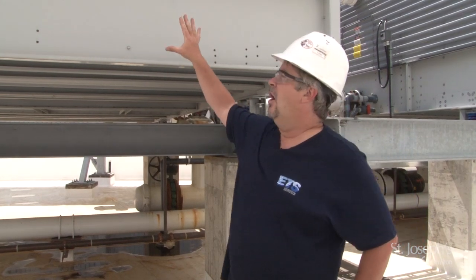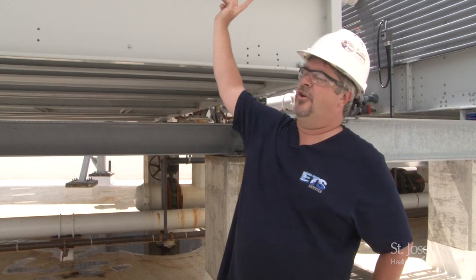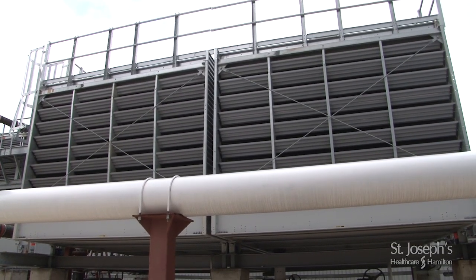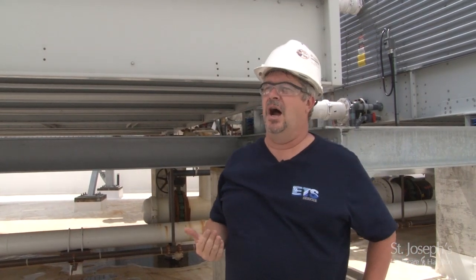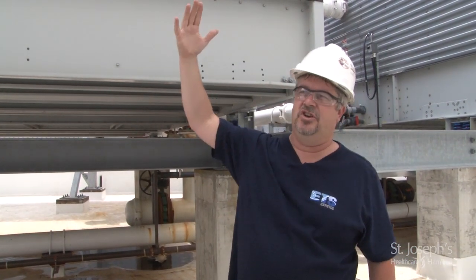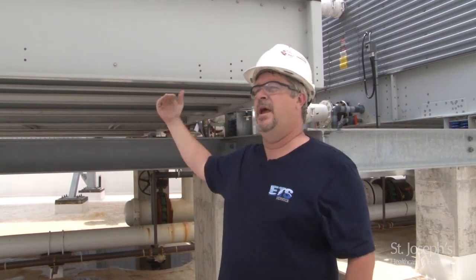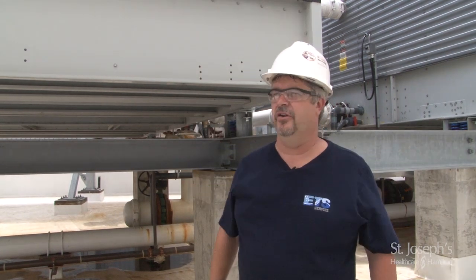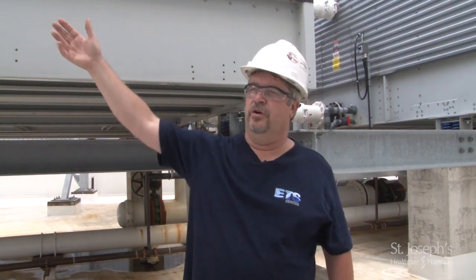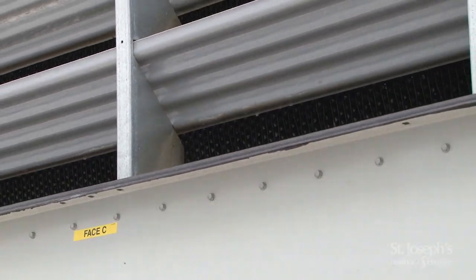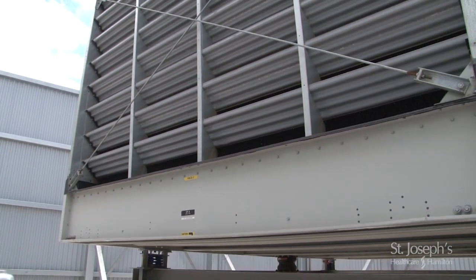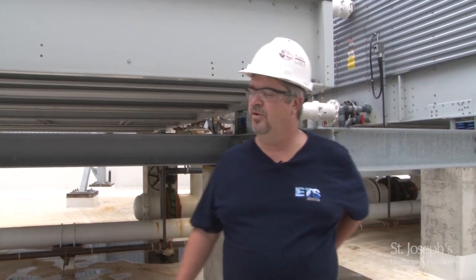On the maintenance of this area, as we're still talking about pressure washing, these gray plastic louvers you see in front of the tower, their sole purpose is if there is any splash out coming from the fill pack, it will grab it and push it back into the tower so that we don't have water splashing out and over. Those louvers can be washed with a pressure washer. You should try and keep them cleaned up. That's an annual maintenance of a cooling tower. You wash off those louvers, try and keep them nice and clean so they don't break and fall apart on you. From this side of the tower, I want to move over to the side where we can have a look at some of the connections and safety features of the cooling tower.